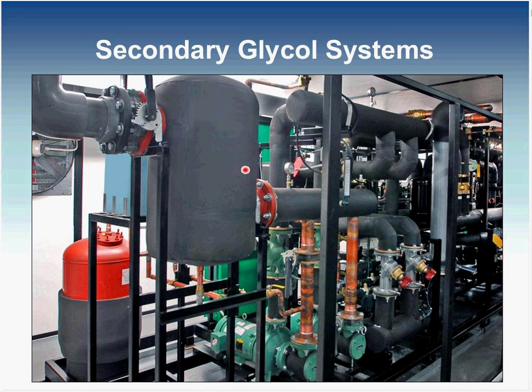Okay, the next thing someone might ask is, how come it's less likely to lose large amounts of refrigerant with a glycol system? We already touched on it a little bit. First, it's a centrally located type of system. You have the rack at one end of the facility, the pump at one end of the facility. So you're looking for leaks down here, or on the wall back over here at the compressors, and you're only checking for leaks there. So it's pretty fine.